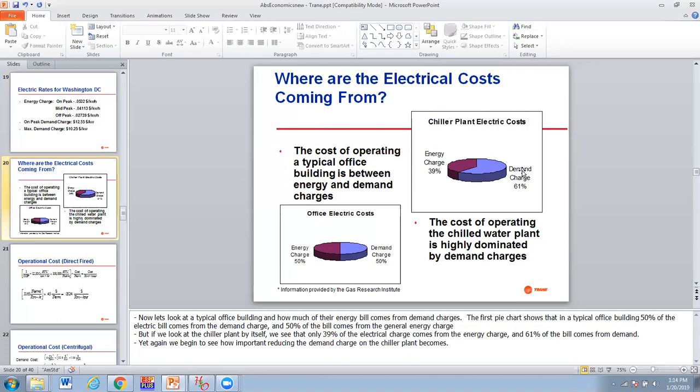And that's what goes into what they call a hybrid chiller plant, where you have absorption and centrifugal units working together, which gives you some flexibility. That mix addresses the fact that demand charge is typically high on the chiller plant.